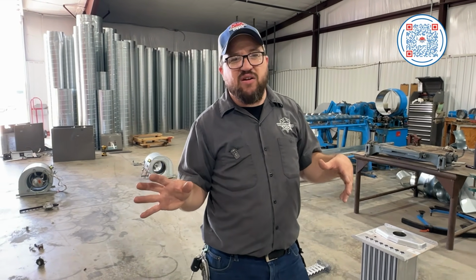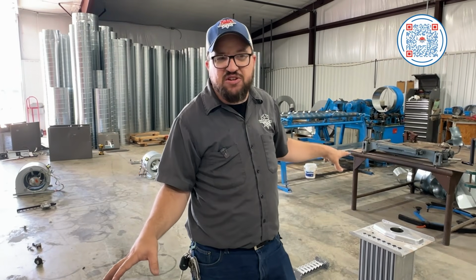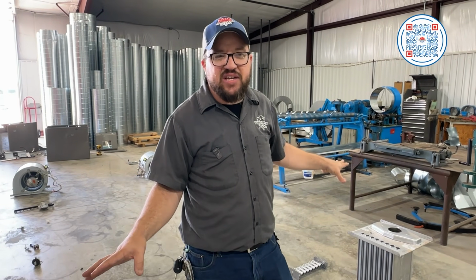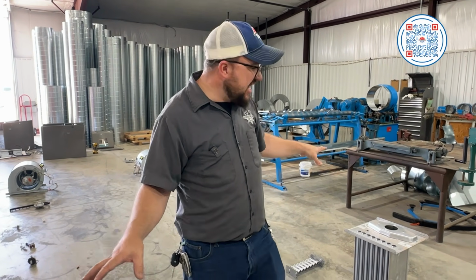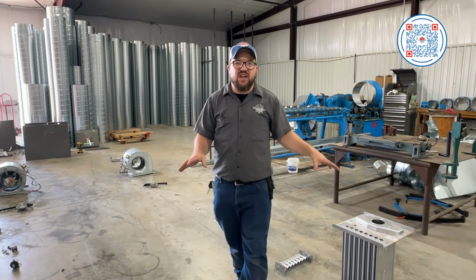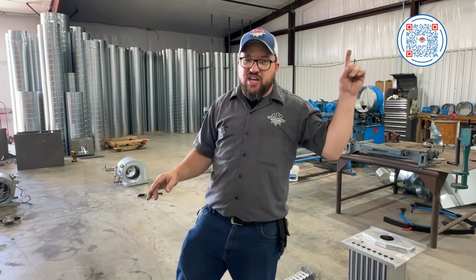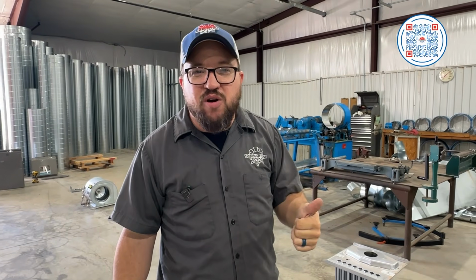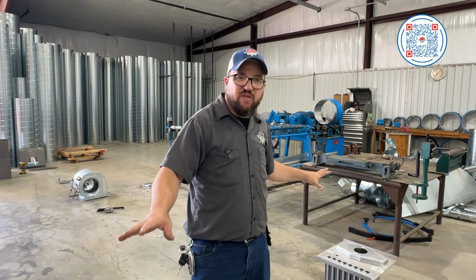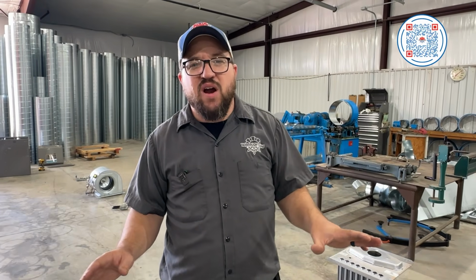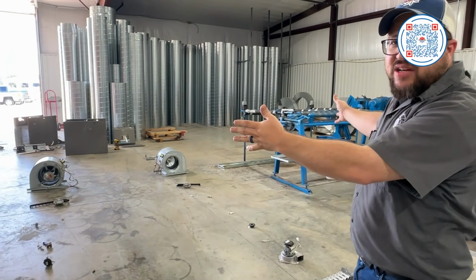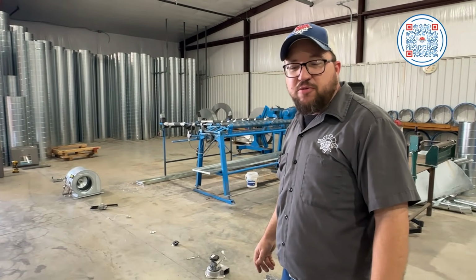I hadn't done one in a while. Usually when we get to the point where the heat exchanger's going bad, it's usually out of warranty, and that's a pretty big ticket item. Anytime a big ticket item like that comes up, I suggest you scan that QR code and get a quote on what a new unit would be, because that estimate will give you a pretty good idea of what you're going to need to change out. If you're looking at spending $3,000, $4,000, $5,000, why would you put that into a unit that's got tons of other parts that probably need to be changed out too?